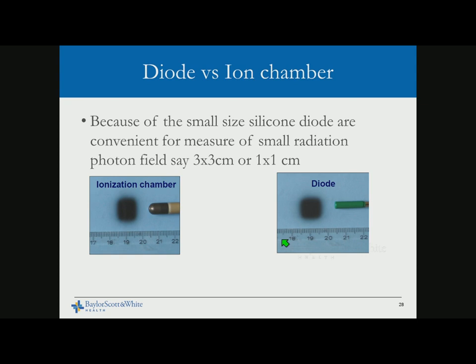When using output measurements, be careful with small field output. For field sizes of 3×3 or 1×1 cm, a silicon diode is much better compared to an ion chamber due to volume averaging effects. Because of its small size, the diode is better suited for small fields. However, you must be aware of diode over-response to low energy photons due to the predominant photoelectric effect — choose the right tools for your measurements.